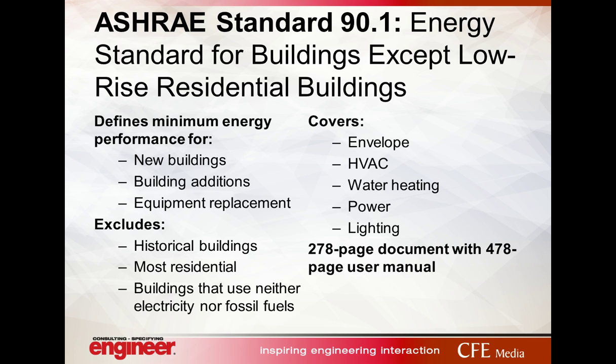It's new constructions, major additions. If you're replacing an air handler or a chiller, it governs all of those. It's not retroactive though, so it doesn't retroactively apply to any of your hospital facilities, but new projects it will. The exclusions probably won't apply to any of your projects. It's really just for residential or historical buildings or shacks that don't use any energy at all.